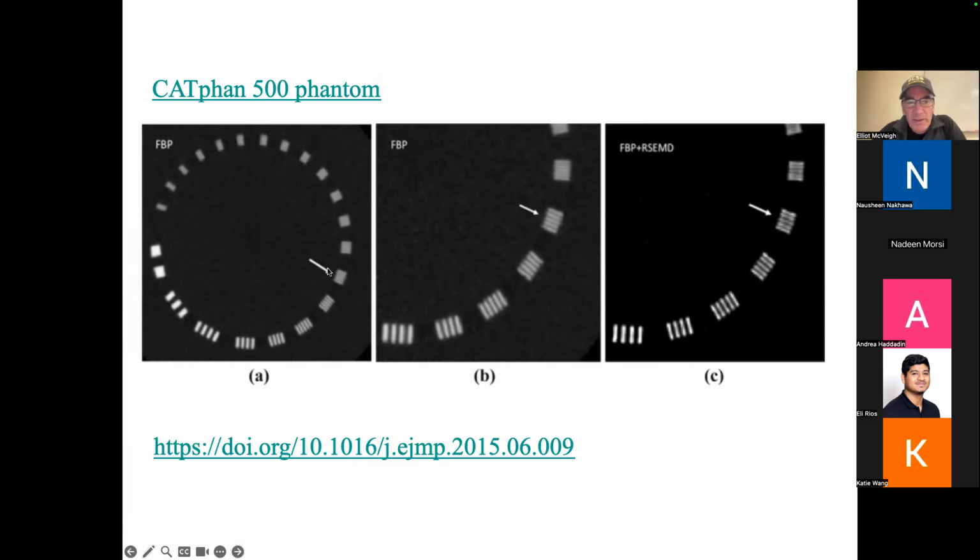And then we look through and we say, okay, by the time I get here, I don't see bars anymore. So this is basically my threshold for spatial resolution, maybe even this one, right? This is where it really starts to cut off. And so at this frequency, in cycles per millimeter, that's where this thing's cutting off.